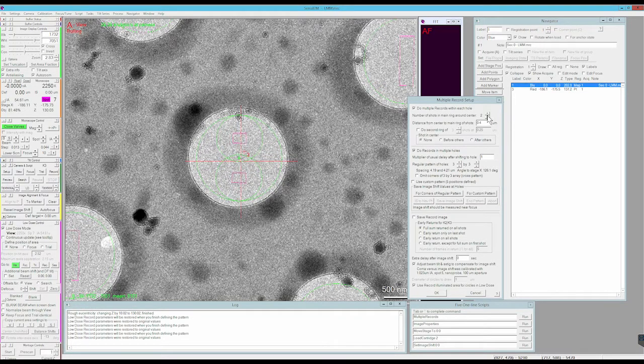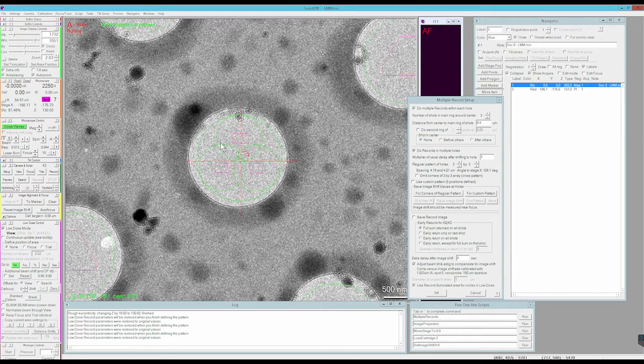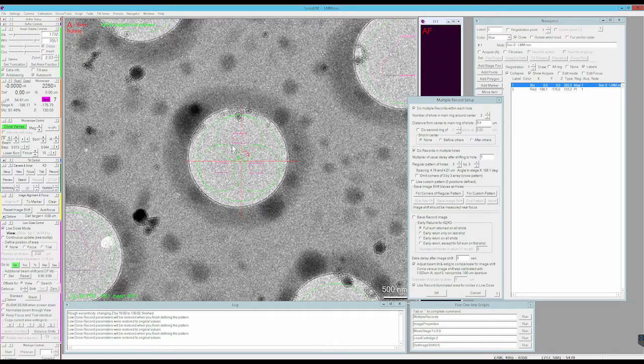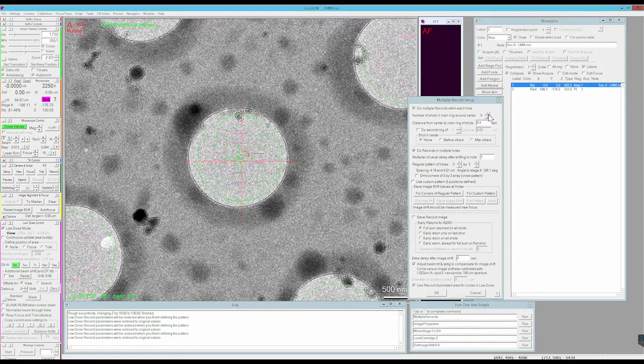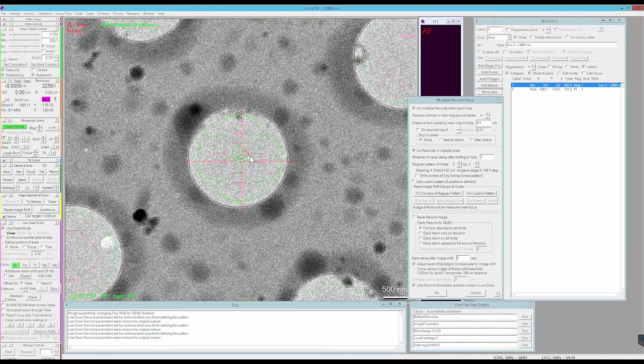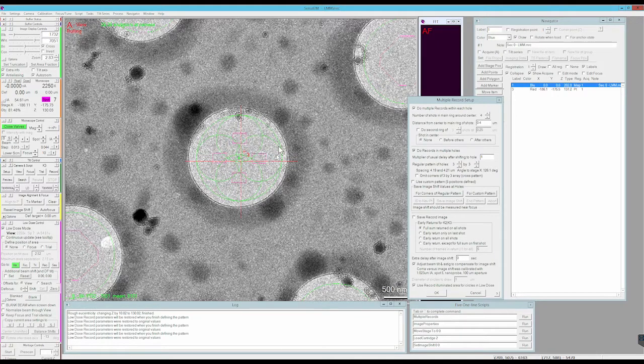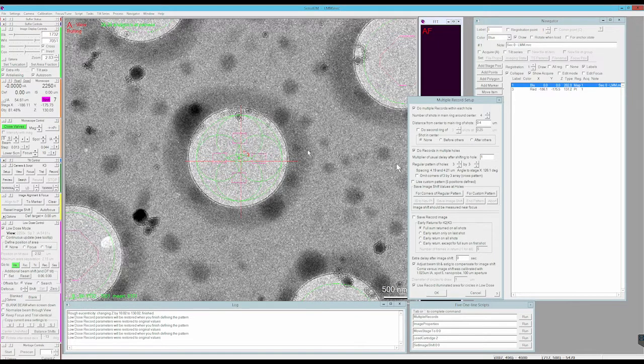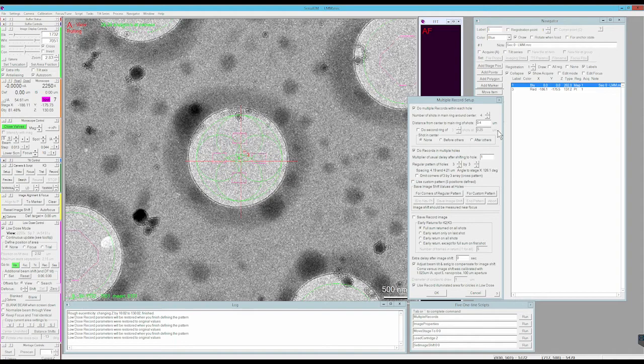Let's increase the number of acquisitions in this hole. There's still some more space. So I'll click three, and we're seeing that there's no overlap of a beam into the field of view. Let's see what four looks like. So with four I'm now starting to get beam going into the field of view of my camera.